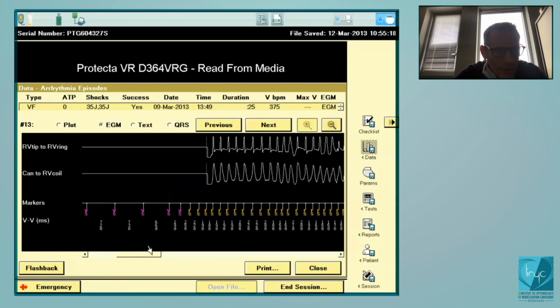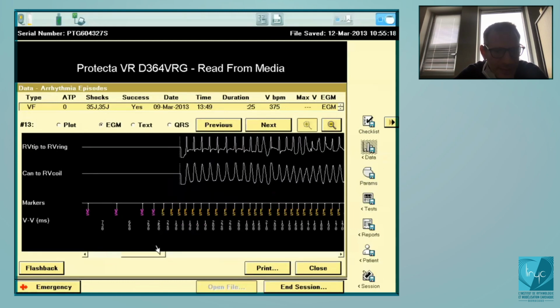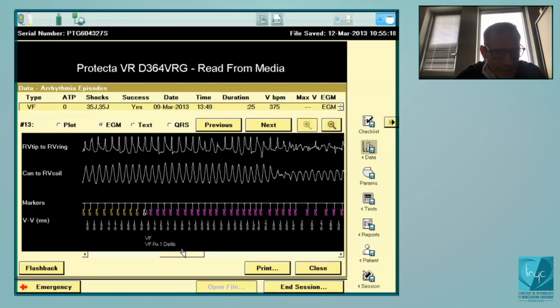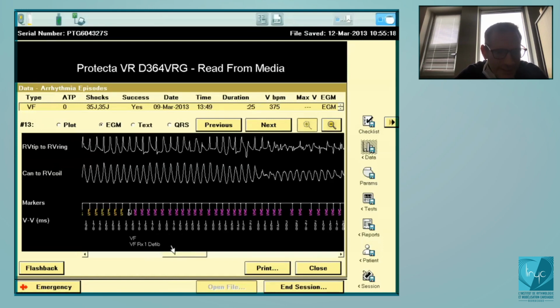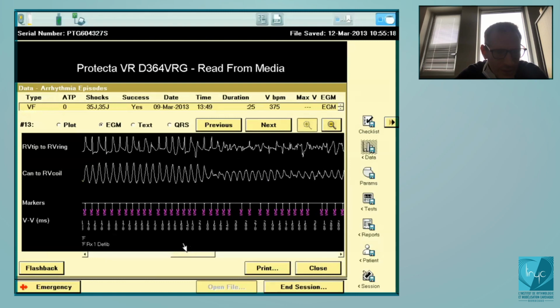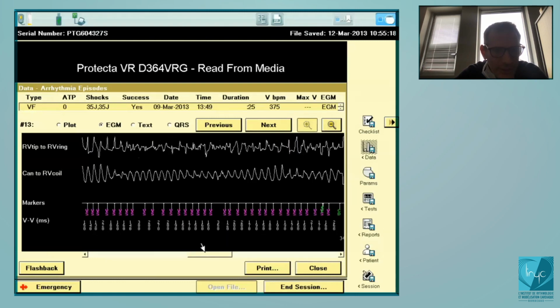So once more, initially normal rhythm, and then acceleration, polymorphic tachycardia. Then the first counter is a probabilistic counter, 30 out of 40. And once it's filled, then detection of the episode, then charge of the capacitor. You see here that there is a little undersensing. You see some long cycles. These are the ones where the dot was out of the VF zone.